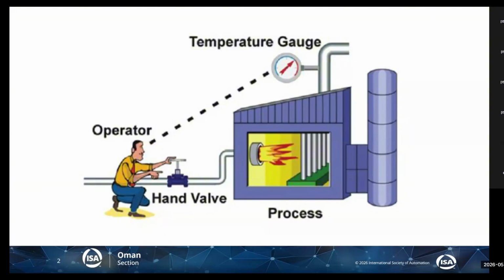If you can see in the picture here, the plants before PID controllers were running on manual intervention. You can see on the right side, here's the operator, and here's the furnace. He is looking at the gauge, and based on this temperature, he will open and close the fuel valve. For example, if I have a low temperature, he will open more fuel gas to have a higher temperature in the furnace, and vice versa. If I have a high temperature, I will close the valve.